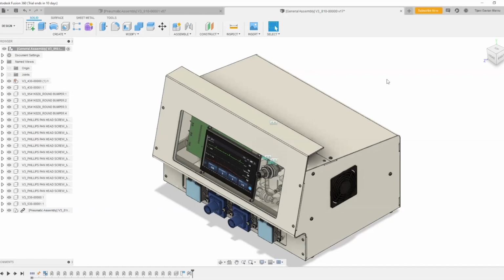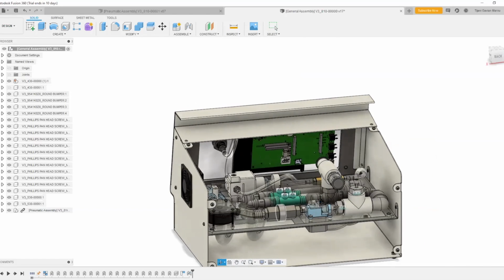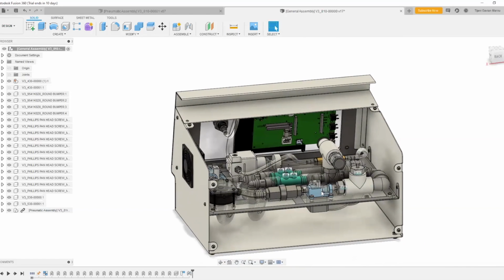We wanted the ventilator to be as modular as possible. All of the ventilator's internals are mounted to a frame that can be removed as one piece. In fact, the entire functional unit can be assembled outside of the enclosure. The enclosure was also designed around maintenance, with removable panels allowing access from all sides. The internal assembly can be seen here.